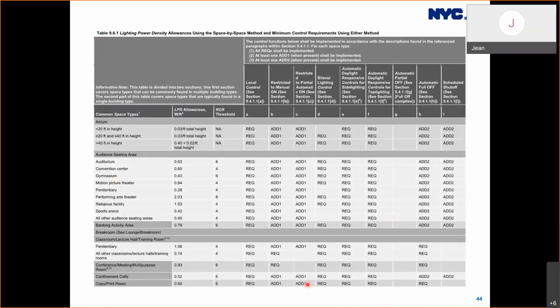9.6.1. So while lighting control provisions in ECC are rather descriptive, ASHRAE has listed the controls requirements in this nice tabular format, space by space. So with ASHRAE, it's relatively easier to identify what kind of controls are required in particular spaces. So lots of information is packed in this table. A little later, we'll go over briefly how we use this table for controls requirements.